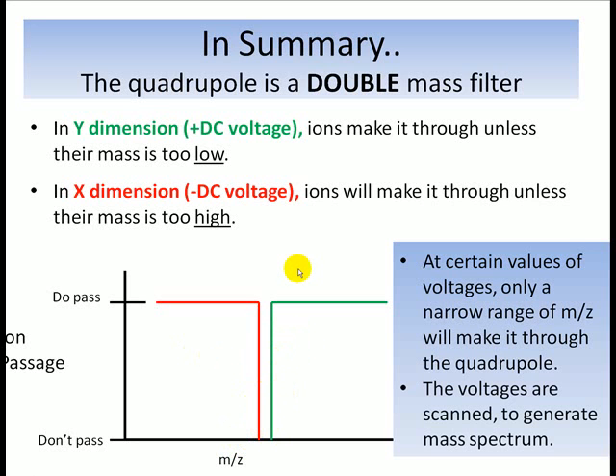And of course, what we want to do with the quadrupole mass filter is create a mass spectrum which detects ions of all different mass charge ratios and also sort of quantifies how many ions of each type there are. So we want to be able to scan through the entire mass charge ratio range from low to high. And we want to do this ideally pretty quickly so that we can do low to high scans over a bunch of times and then maybe do something like ensemble averaging to add those scans together.